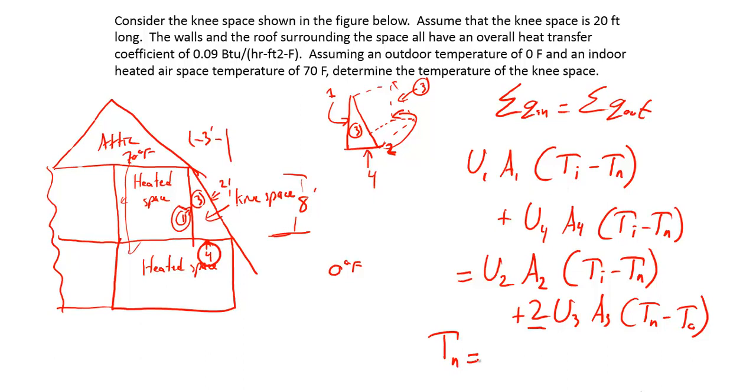What you're trying to solve for is the temperature of the knee space. We have the inside temperature. U1, A1, U4, and A4 is the difference between the inside temperature and the temperature in the knee space. You're trying to solve for T sub N. For the walls that share surface of the outside, which is surface two and three, it's the difference between the outdoor temperature and the knee space. If you do all the math and you solve for the knee space temperature, you should get 32.7 degrees Fahrenheit.